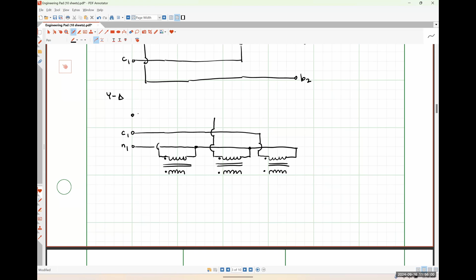Unless I've made a mistake I don't see, the primary coil here is between the A and the neutral, this one is between the B and the neutral, and this one is between the C and the neutral, exactly like we should expect. Once again, the dots are on the side away from the common neutral conductor, so we're good there.